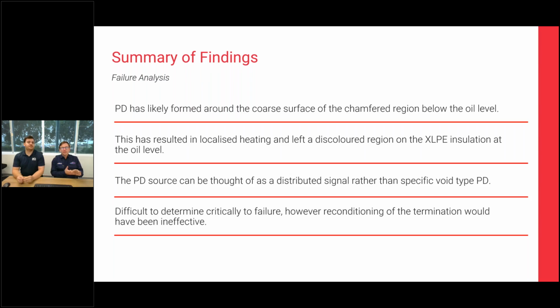So we'll go into the summary. The summary of findings with the failure analysis is, as we just spoke about, PD was likely formed around that coarse surface of the chamfered region, just below the oil level. This has resulted in localized heating and left that discoloration on the XLPE insulation. The PD source can be thought of as that distributed signal rather than a specific void type partial discharge that you would commonly see in other HV assets, such as current transformers, voltage transformers, or power transformers.